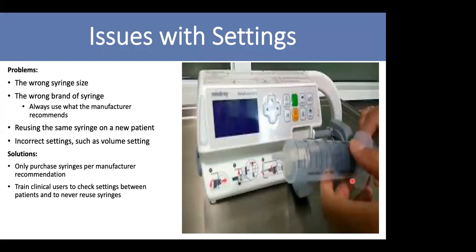At the same time, this can also cause alarms because the syringe line may become soft or very hard. Once you use a syringe and try to reuse it, you try to dry it, so the line becomes harder and you're going to get occlusion issues. Incorrect settings, such as the volume setting on the syringe, can cause alarms as well. So the solution is basically to purchase according to the manufacturer's recommendation, train the clinical user to check the settings between patients, and never reuse the syringe again. Train the user how to do proper setup to avoid unwanted alarm errors.